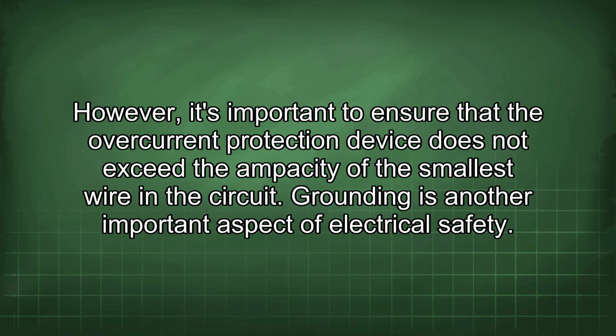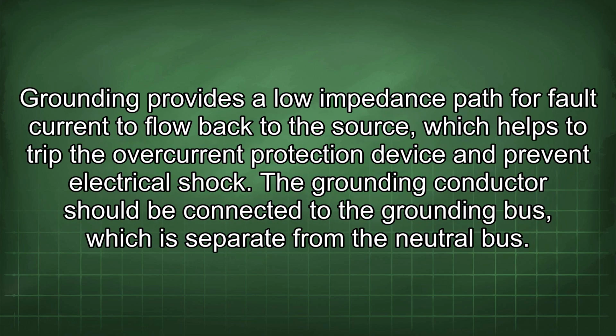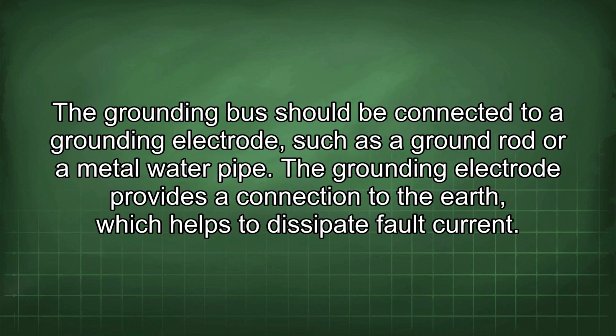Grounding is another important aspect of electrical safety. Grounding provides a low impedance path for fault current to flow back to the source, which helps to trip the overcurrent protection device and prevent electrical shock. The grounding conductor should be connected to the grounding bus, which is separate from the neutral bus. The grounding bus should be connected to a grounding electrode, such as a ground rod or a metal water pipe. The grounding electrode provides a connection to the earth, which helps to dissipate fault current.